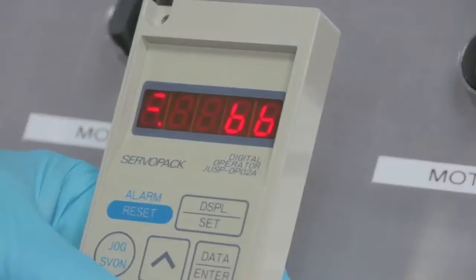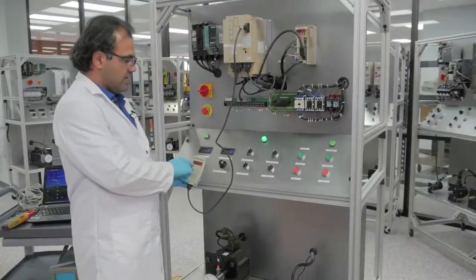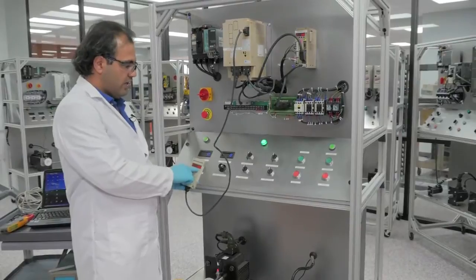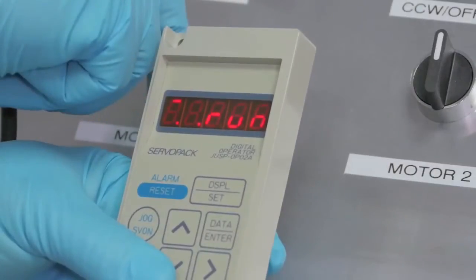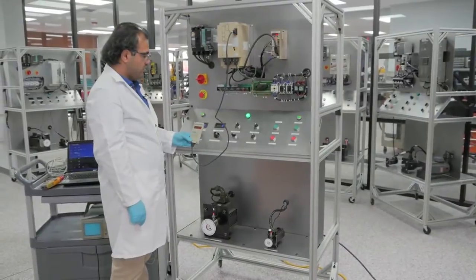As you see you can find the drive didn't have any problems and it's running waiting for the enabling to run. When we enable the drive it's ready to run and waiting for the speed command.